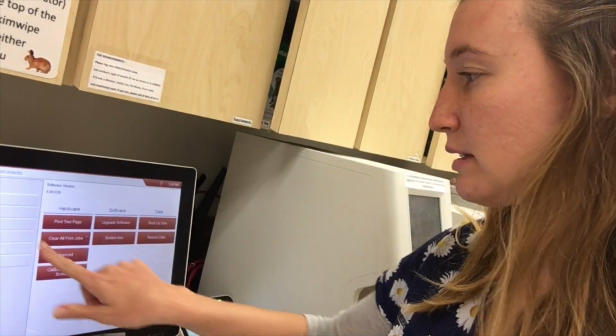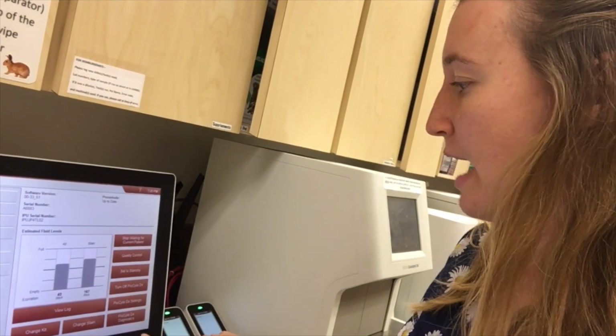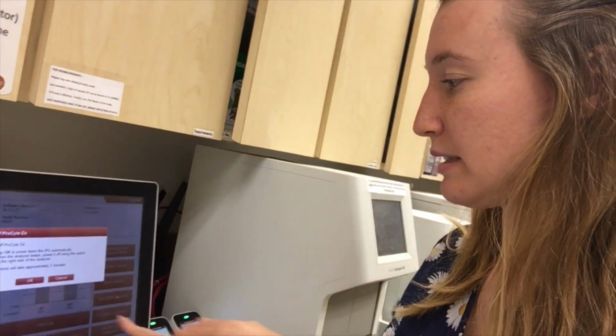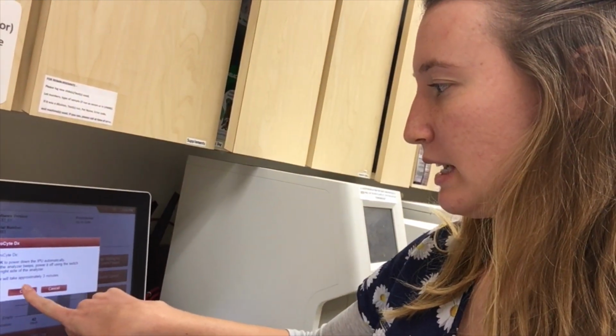So the next maintenance that we're going to do for the ProCyte is turning off the analyzer. This should be done once a week. So I am going to go to instruments, go to the ProCyte, and turn off the ProCyte. Okay, so it says it's going to take about 3 minutes to turn off. At that point, we are going to clean the analyzer.